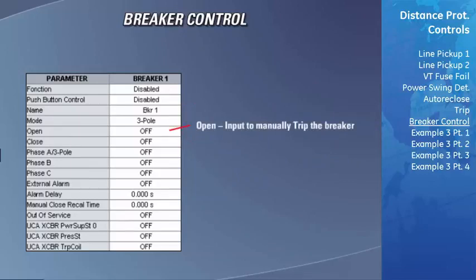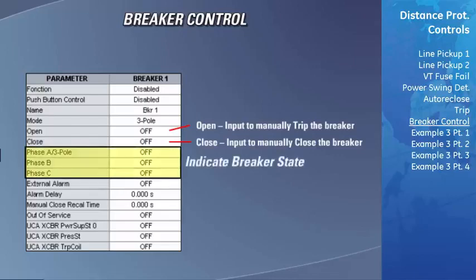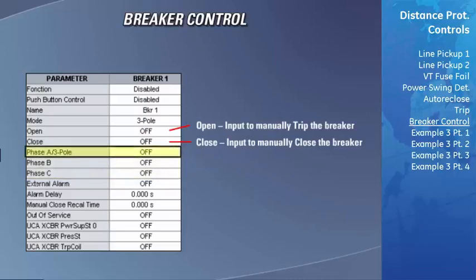The open field specifies the D60 input that is used to manually trip the breaker. This will also normally be a contact input, a virtual input, or the result of a flex logic equation that ORs these two inputs together. The close field specifies the D60 input that is used to manually close the breaker. This will normally be a contact input, a virtual input, or the result of a flex logic equation that ORs these two inputs together. The next three fields are used to indicate the state of the breaker to the breaker control function. If 3-pole tripping is used, only use the field labeled phase A/3-pole.